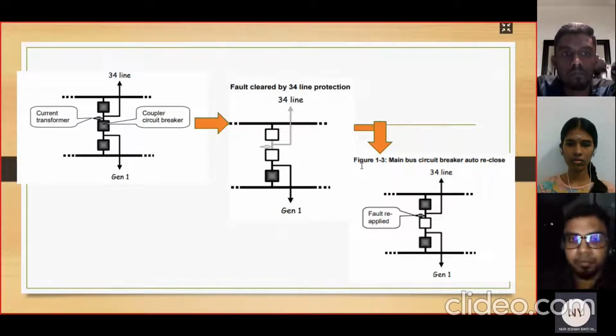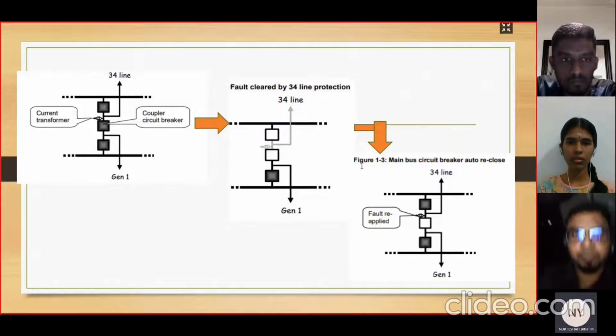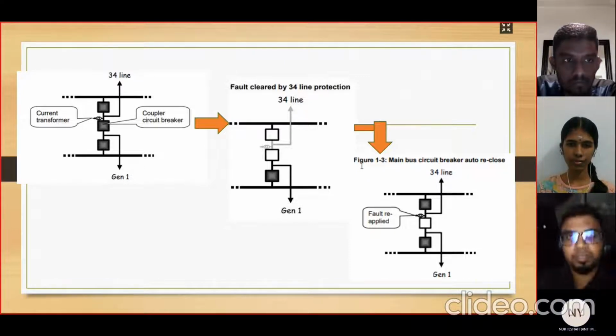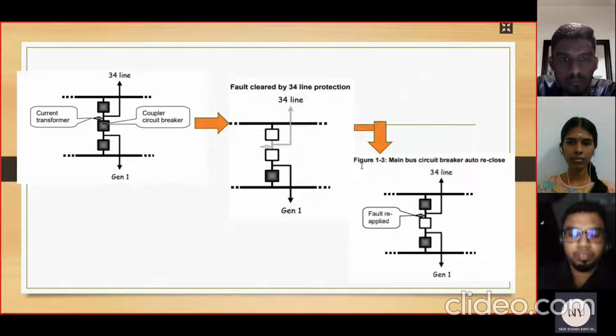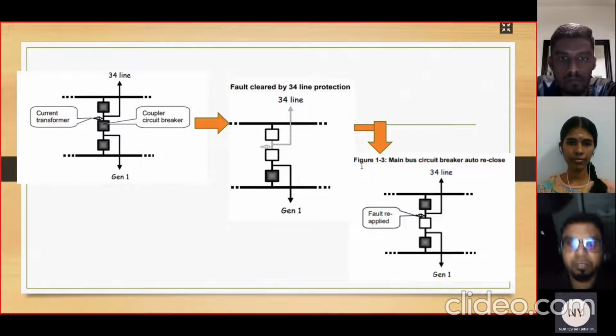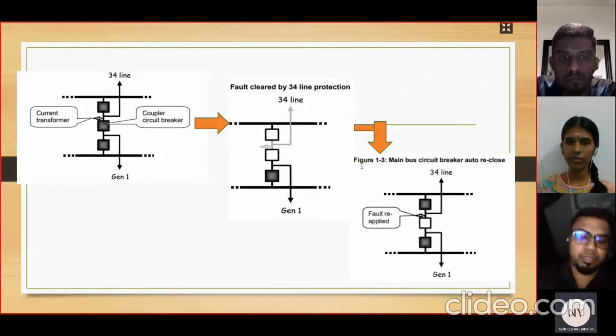This figure shows how the protection system happened. They open the circuit breaker and close it, and then in the third picture, the circuit breaker reclosed and the fault was reapplied to the system.